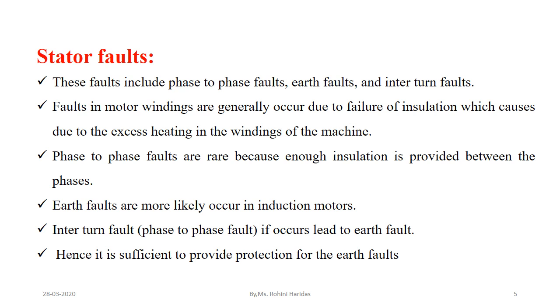If a short circuit or overload occurs, the magnitude of current in the winding increases. As current increases, I²R losses also increase, causing temperature to rise. Because of the increased temperature, the insulation may fail, which can cause phase faults, phase-to-phase faults, or interturn faults.